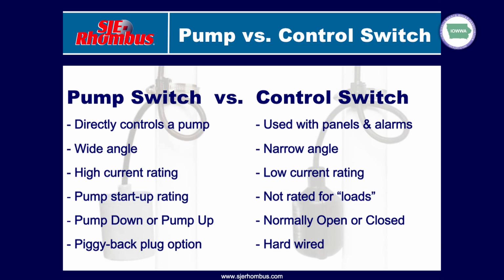Wide angle switches are going to be used exclusively with pump switches. On a control switch, it's going to be a narrow angle of activation. Pump switch, as we already alluded to, the pump switch is designed to handle full load, full current to operate that pump. With a control switch, it's going to be limited to very low amperage, low current going through the switch.